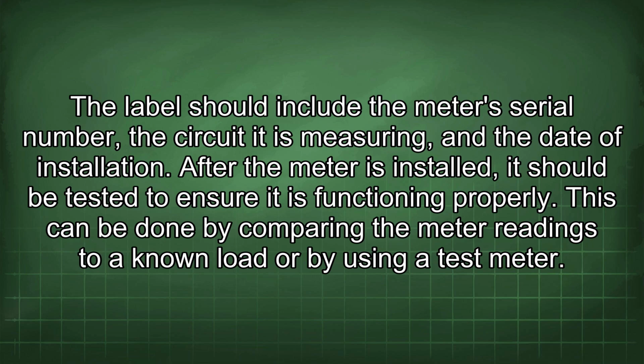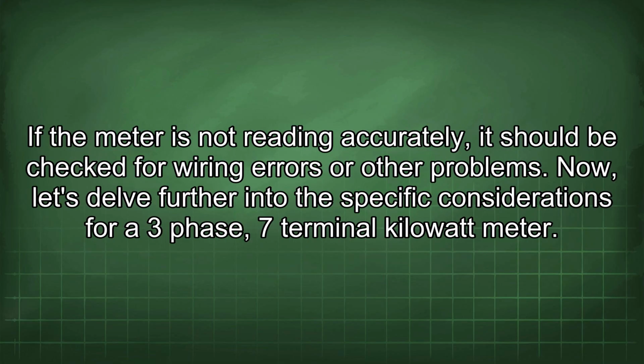After the meter is installed, it should be tested to ensure it is functioning properly. This can be done by comparing the meter readings to a known load or by using a test meter. If the meter is not reading accurately, it should be checked for wiring errors or other problems.